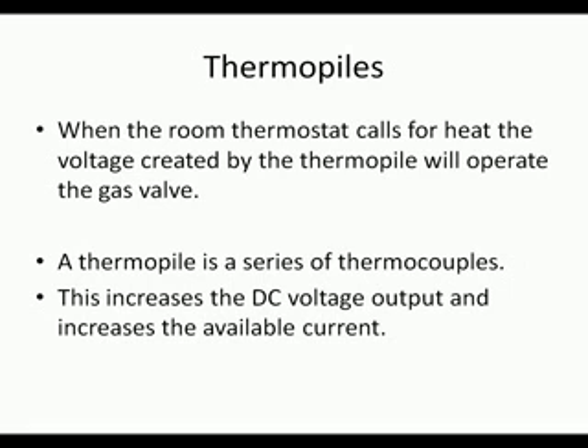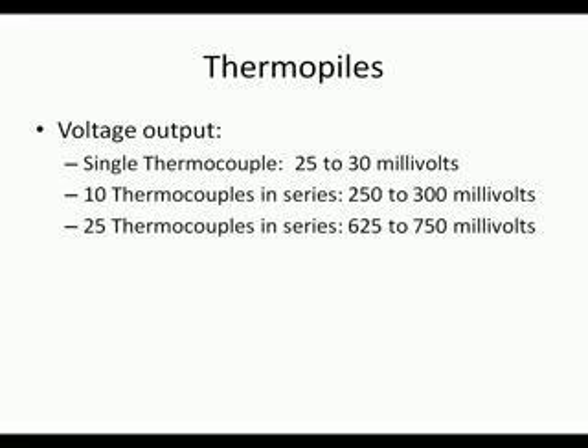The thermopile system is lit the same way as the thermocouple system. The thermopile creates enough voltage to operate the entire burner circuit. The gas valve and the thermostat are wired in series with the thermopile. When the room thermostat calls for heat, the voltage created by the thermopile will operate the gas valve. A thermopile is a series of thermocouples. This increases the DC voltage output and increases the available current.